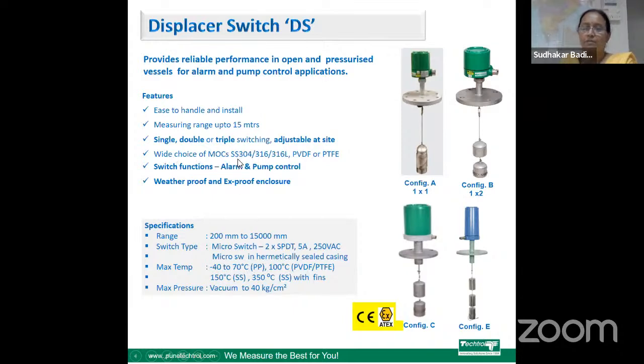A wide choice of material is available in stainless steel, PVDF and PTFE. Switch functions can be used for alarm and pump control applications. The enclosures will be available as weatherproof or Ex-proof protection. The range of this switch is available up to 15 meters. The output of the switch is micro switch, 2 SPDT, 5 ampere at 250 volt AC.